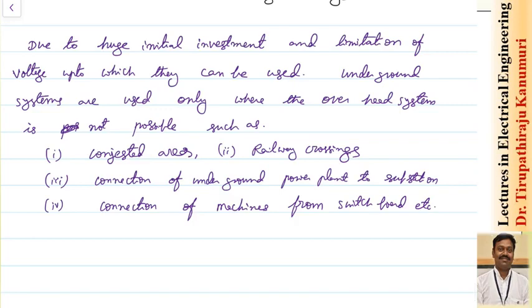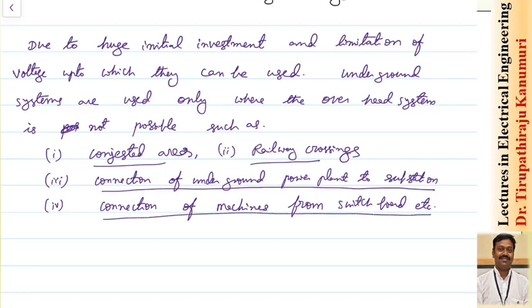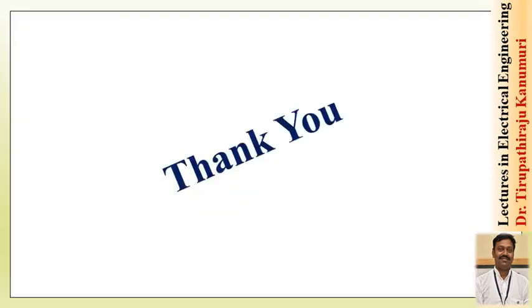Summarizing: due to huge initial investment and voltage limitations, underground systems are used only where overhead systems are not practically possible — for example, congested areas, railway crossings, connections from underground power plants to substations, and connections of machines from a switchboard. For extra-high-voltage transmission, overhead transmission lines are always preferred because bare conductors can be used and the cost is very less. For distribution systems or crossings where overhead lines cannot be laid, we go for underground cables.